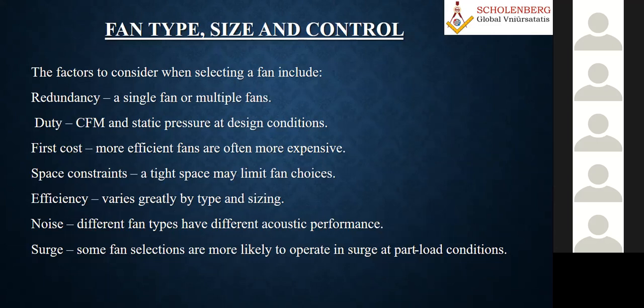And when we are talking about fan type or fan size, depending upon the place, like operation theaters, we may go for duty and even standby, because operation theaters cannot be stopped even for 1 minute or 1 second. Moreover, we need this type of unit running 24 hours. So they also need their regular preventive maintenance, and at that time you have to shut down. So it all depends upon how much redundancy you are planning. So this is all the initial planning stage you have to understand.